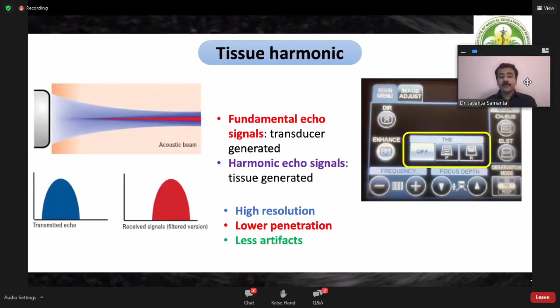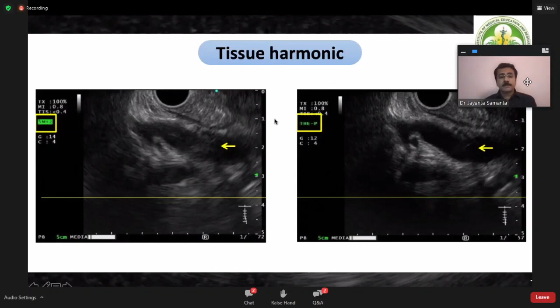I'll give an example. Let's say we are observing a bile duct or a gallbladder, and we find some noise artifacts, and we're not sure. Or when we observe the gallbladder and find a sludge-like material, we are not able to make sure whether it is an artifact or actually sludge. We switch on the tissue harmonic and we get a much clearer picture because the artifacts get reduced, the noise decreases, and we get a much better resolution. So this is an important use of tissue harmonic, where we want a better resolution in anechoic structures where a lot of sound is disturbing. Many times there is a very common artifact known as the side lobe artifact, which I'll come to later. These can be reduced with the use of tissue harmonics.